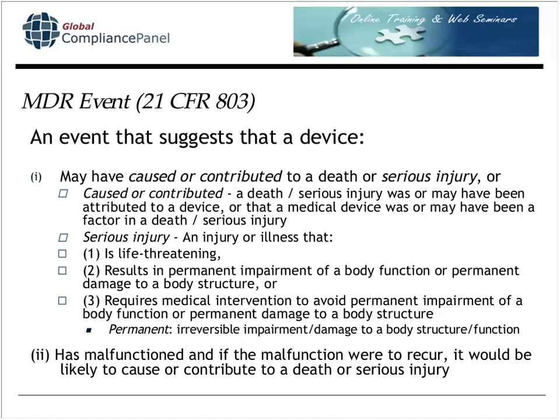However, even if nothing happens to a patient, you can still have an MDR event. In this scenario, your device malfunctions. It just didn't work. But in your opinion, if that malfunction were to recur, it would be likely to cause or contribute to a death or serious injury. So there's a standard of likelihood there, of inevitability, which early on, if somebody gets hurt or dies, if there's any remote chance that your device was involved, you've got to file an MDR. But if nothing happened except for a malfunction, but it's kind of a serious malfunction, the standard of likelihood has to be that it has to be likely that your device would cause or contribute to death or serious injury.